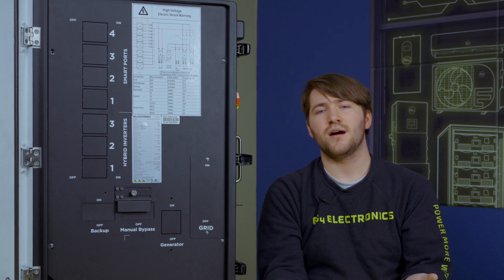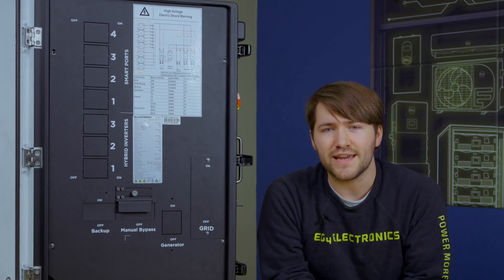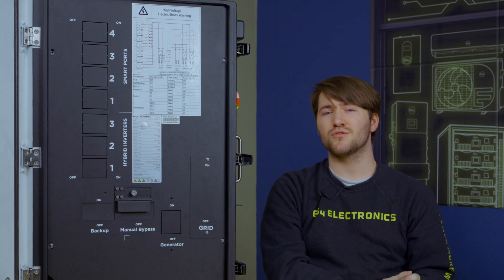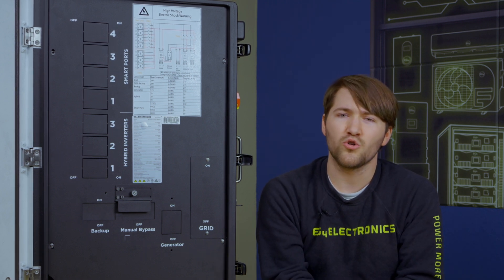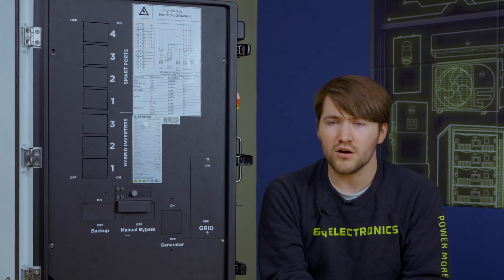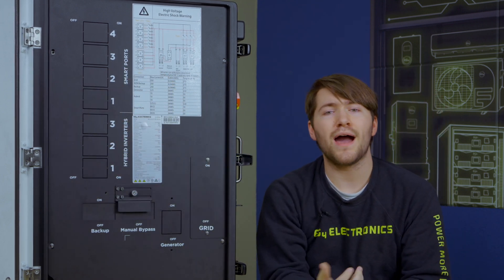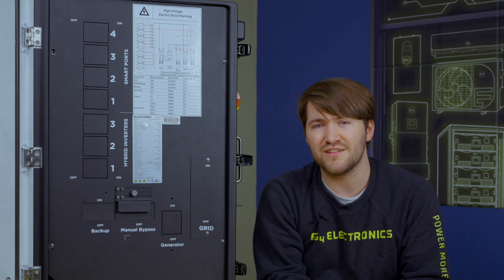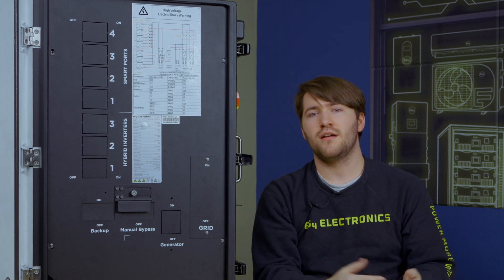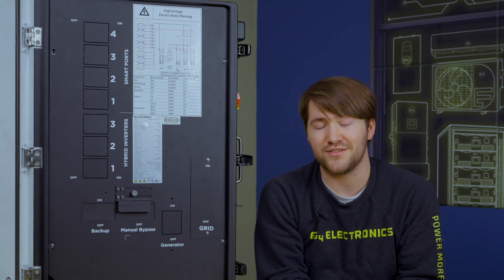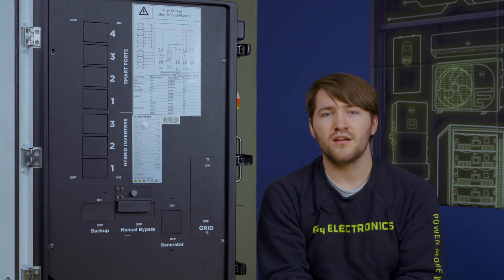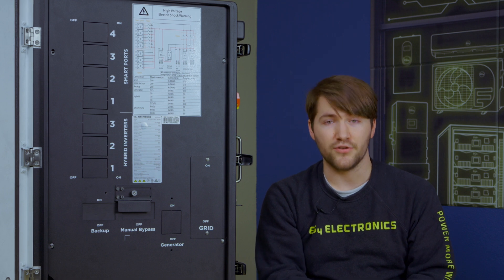What is AC coupling? Well, AC coupling is the ability to put in a preexisting solar system or a typical grid tie solar system, be it micro inverters or string inverters, onto a breaker in here. And it will be powered by your hybrid inverters in the event of a grid outage. This allows your system to actually still produce solar, even when the grid is down, which a typical grid tie system is not allowed to do.